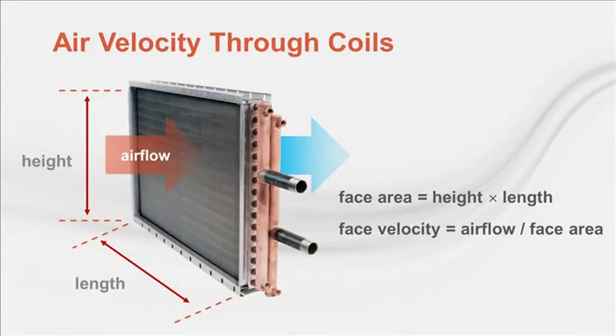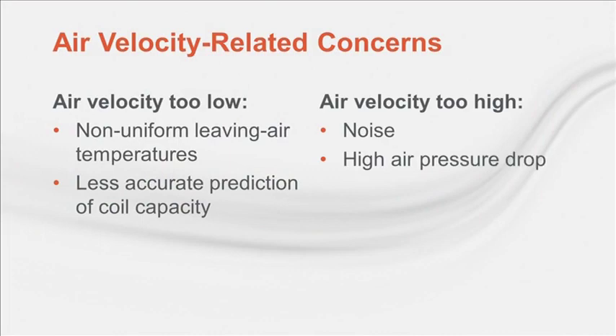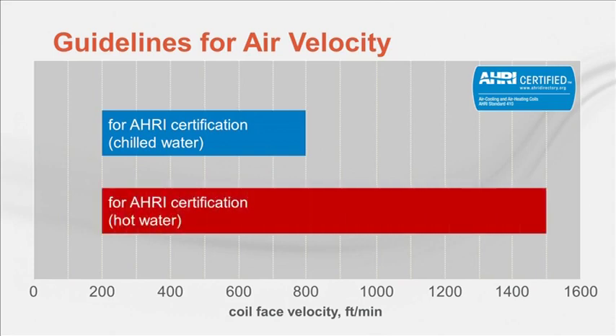Now let's switch from water velocity to air velocity through the coil. The contributing attributes to air velocity are the face area of the coil and the airflow rate. Care should be taken to avoid air velocity that is too high or too low. Risks of too low air velocity include non-uniform coil leaving air temperatures and less accurate capacity prediction. Too high air velocity can contribute to noise, excessive air pressure drop, and increased risk of moisture carryover. AHRI 410 requires cooling coils to have a face velocity between 200 and 800 feet per minute, and heating coils between 200 and 1,500 feet per minute.